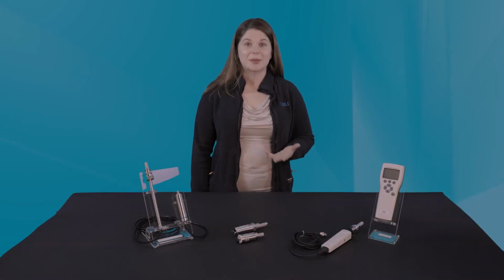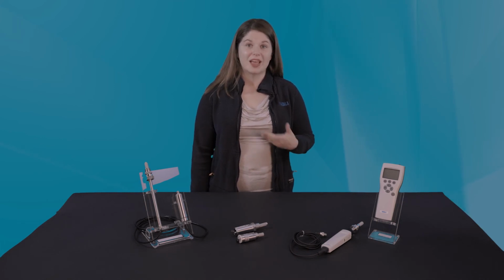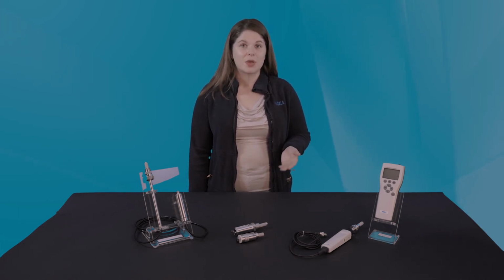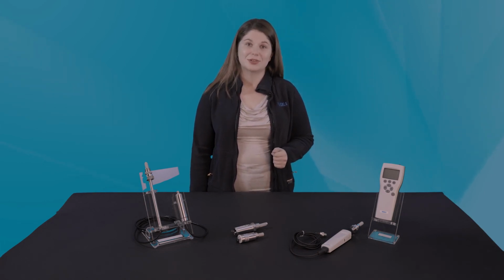In addition to use with the standard DM70 probes, the MI70 indicator can also be paired with any of the compact dew point transmitters mentioned earlier. In these cases, the combination can be used as a portable analogous to the DM70 or for the specific purpose of checking calibration on permanently installed Vaisala transmitters.